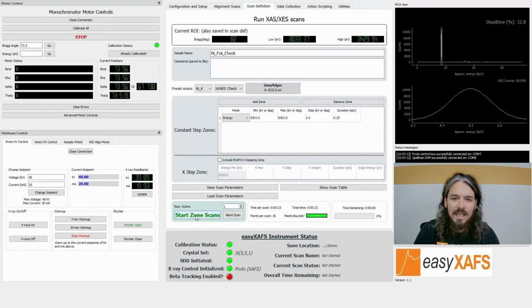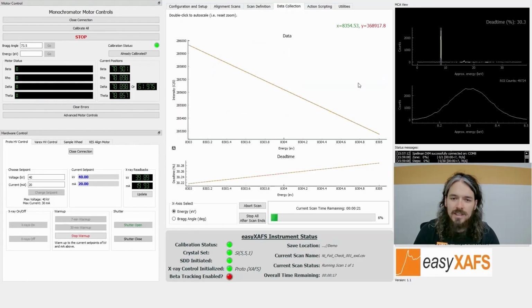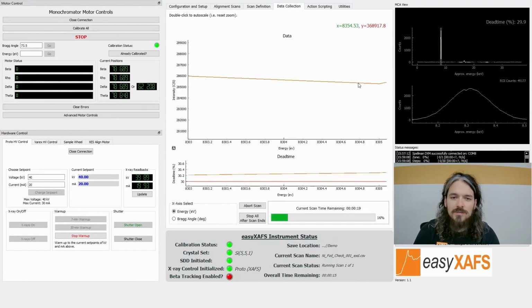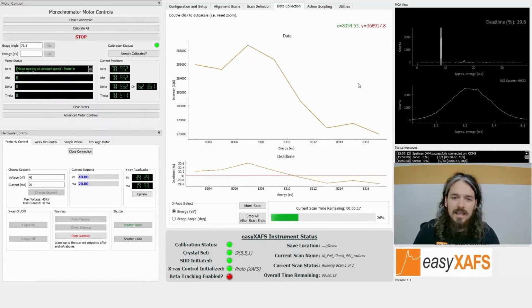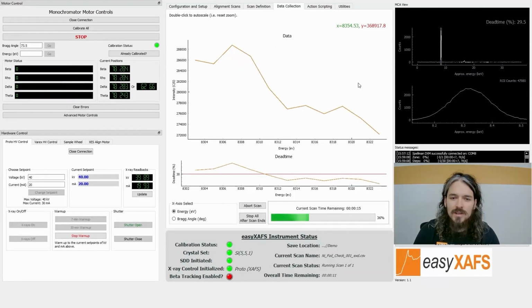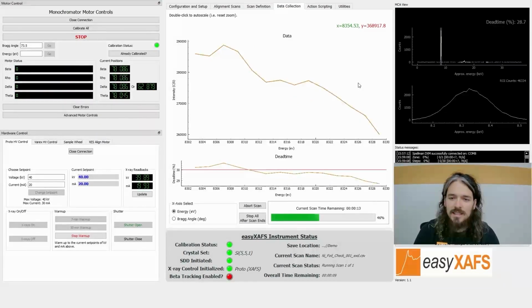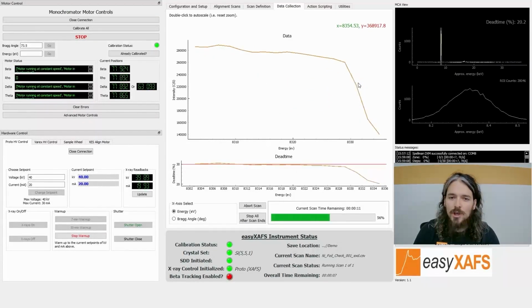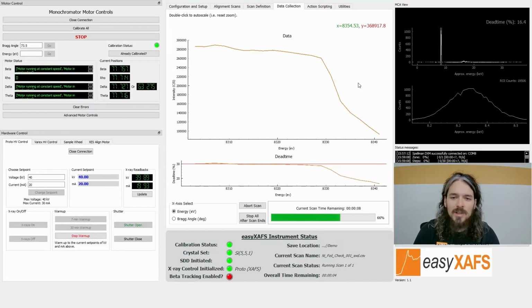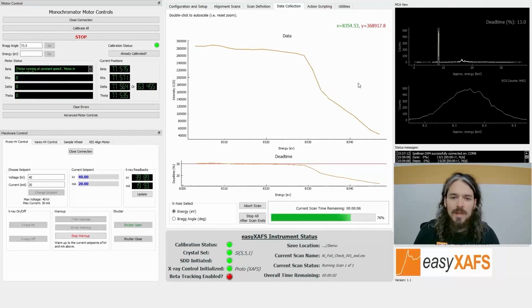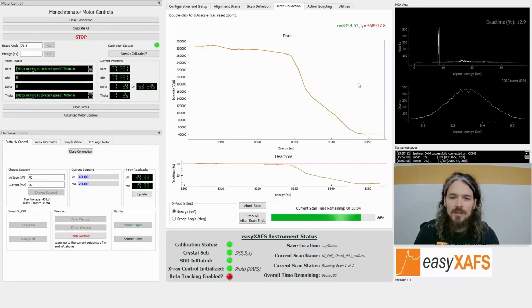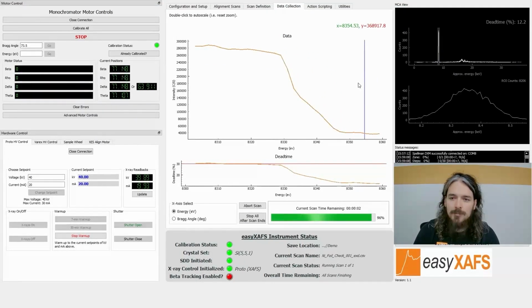Now I'm ready to go ahead and hit start, and the data starts collecting. I'll just fix the auto scale on the plot, and now we can see the counts coming in. We start around 260,000 counts per second, and you can see there's a sharp dip in the X-rays being measured by the detector as we increase the energy past the absorption edge of the nickel foil. And that's just what we expected to see.